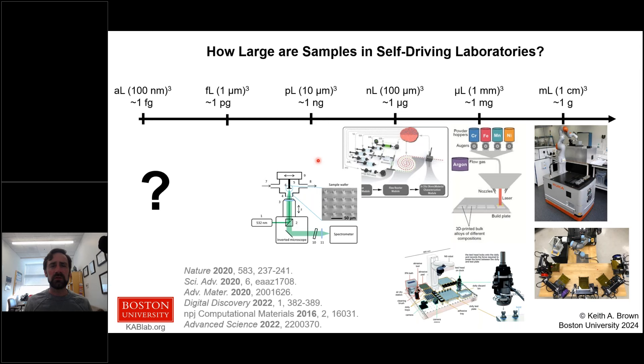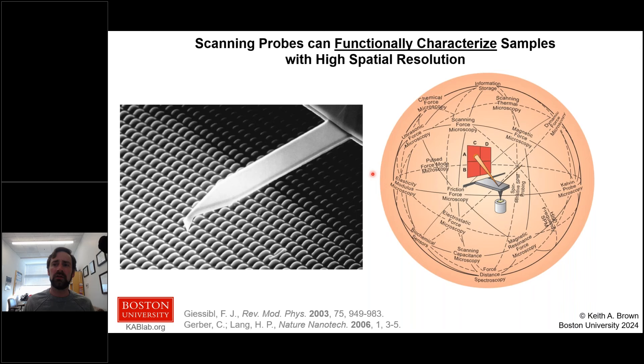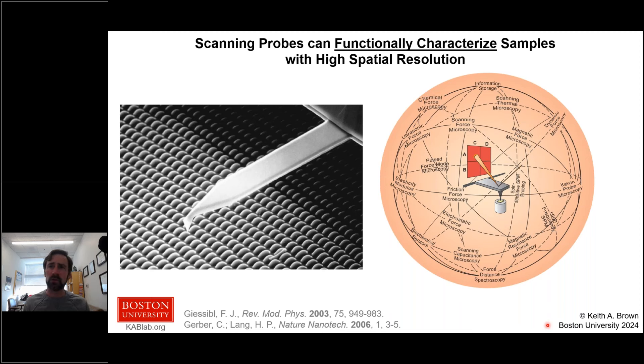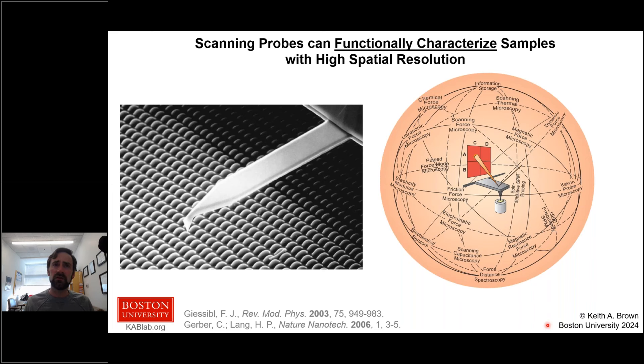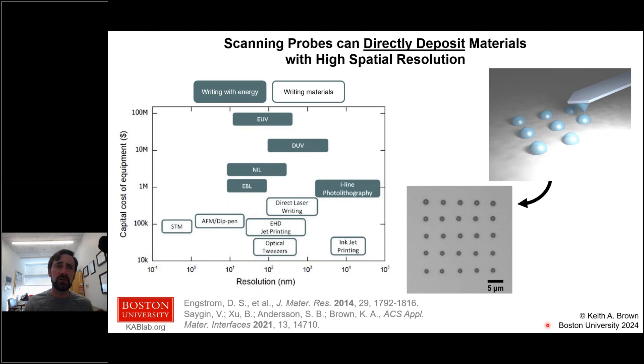To interrogate samples at the femtogram scale, we use the scanning probe microscope. This instrument allows you to position a very fine tip with extremely high spatial resolution and measure and apply all sorts of signals — electrostatic, magnetic, force signals — to do friction measurements, chemical force measurements, and more. It's essentially a multimodal probe that can position in three dimensions with nanoscale resolution.